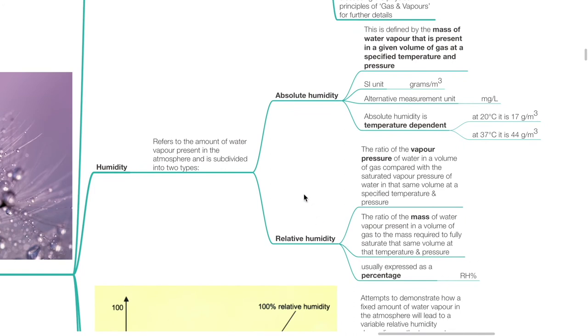Humidity refers to the amount of water vapor present in the atmosphere and is subdivided into two types: absolute humidity and relative humidity. Absolute humidity is defined by the mass of water vapor present in a given volume of gas at the specified temperature and pressure. The SI unit is grams per meter cubed; an alternative measurement unit is mg per liter. Absolute humidity is temperature dependent: at 20°C it is 17 g/m³, and at 37°C it is 44 g/m³.